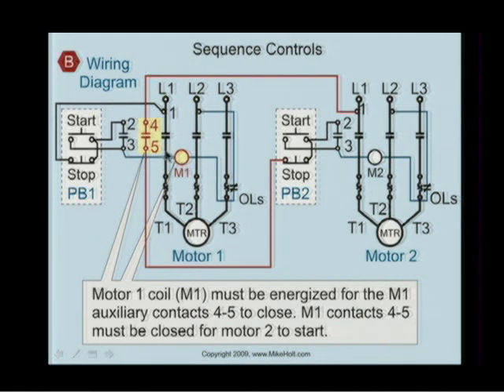It latches that coil. Then I use, and you said this, Dennis, that you can add auxiliary contacts, normally open or normally closed or whatever you want to. So we added a set of contacts, and then we came over from this second motor, and we go through the auxiliary contact on the first motor, that if the first motor is running and this contact is closed, then we're going to get voltage to the start-stop button of the second motor. And if, permissively, we get voltage here, press the start button, get me voltage to the M2, because M2 already has the voltage on the other side from the L2, energize the M2 coil, close the M2 auxiliary contact, which then interlocks the M2 coil.